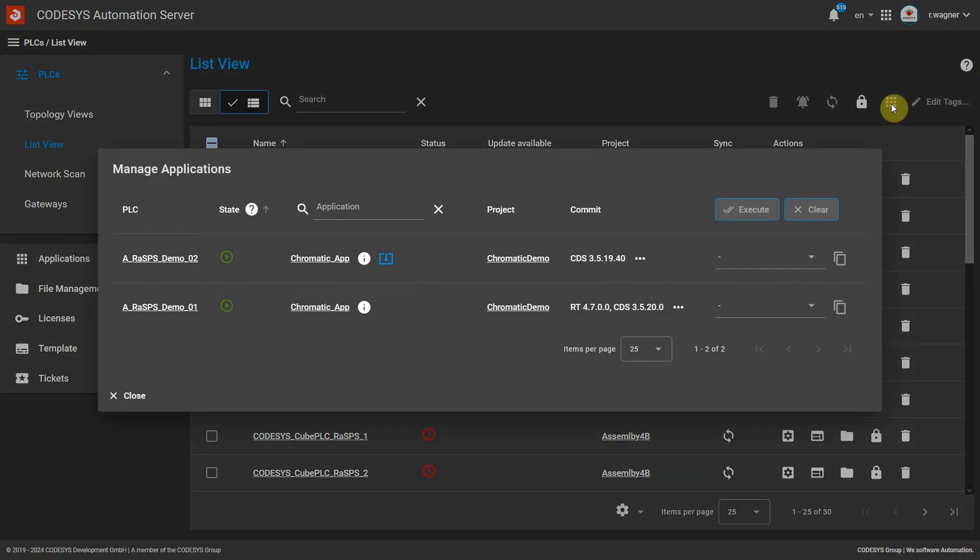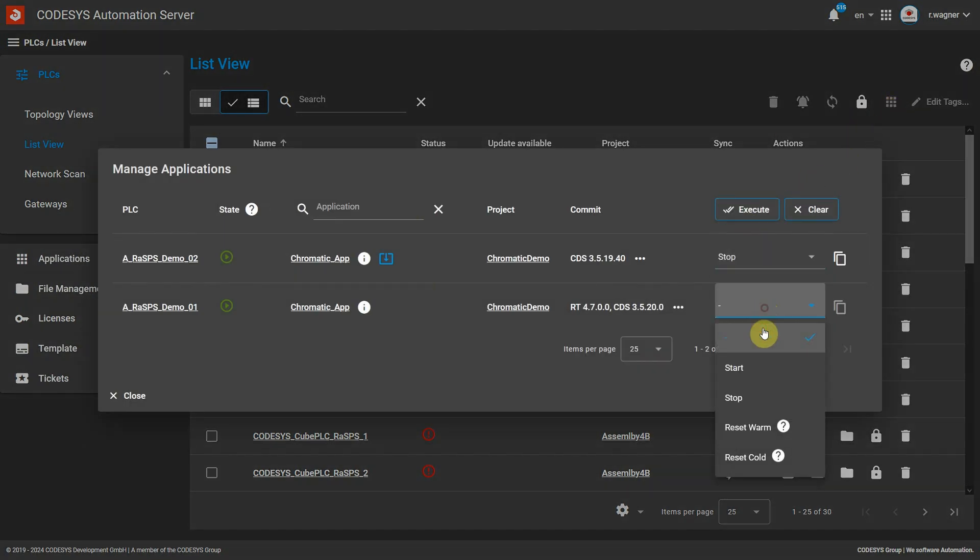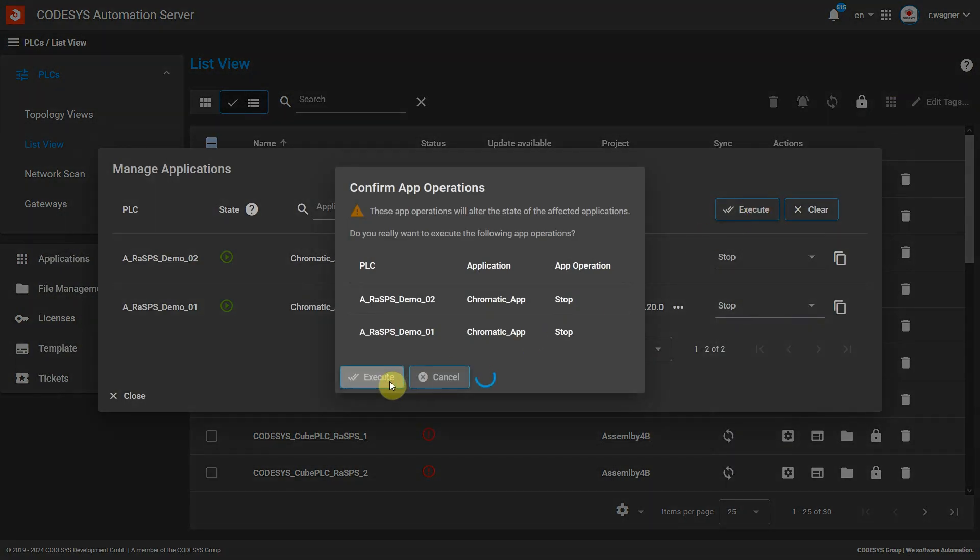You can now start, stop and reset applications on remote PLCs in the web app, even on multiple controllers at the same time. Expired edge gateway certificates can now be renewed via a specially created connection, meaning affected edge gateways are once again connected to the automation server with full functionality — all directly via a web app in any standard browser.